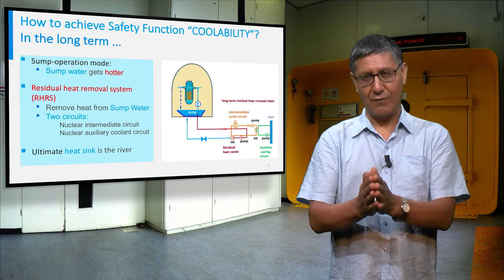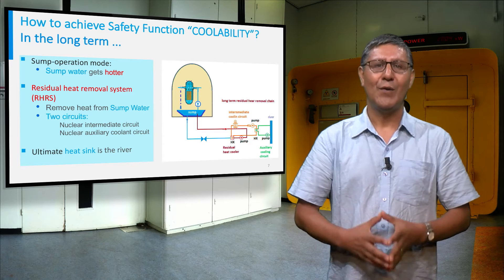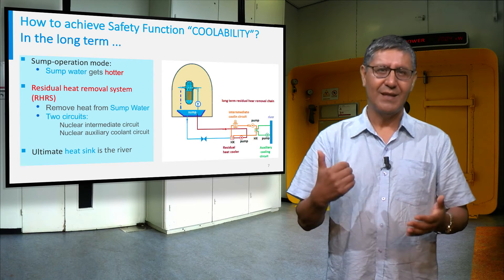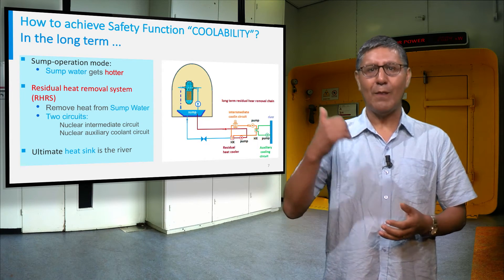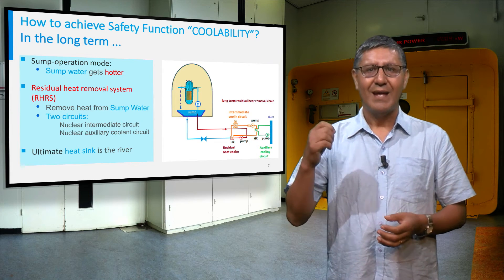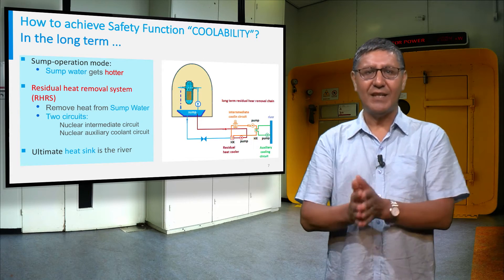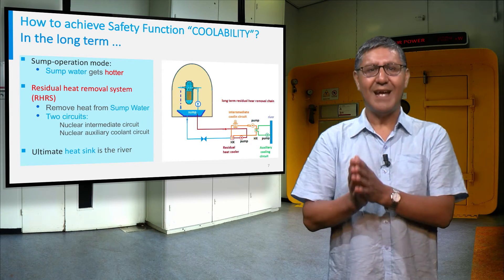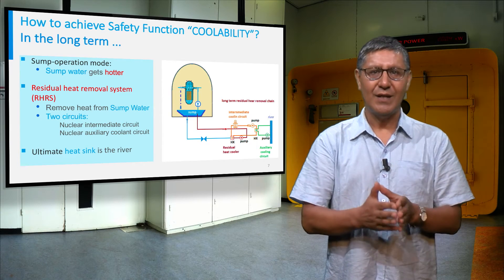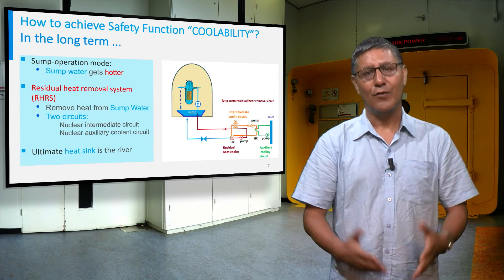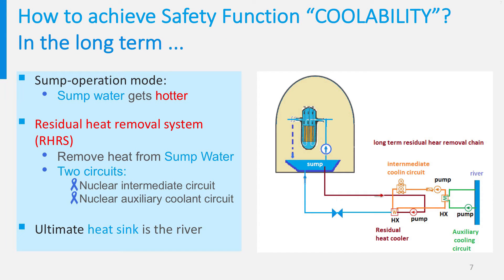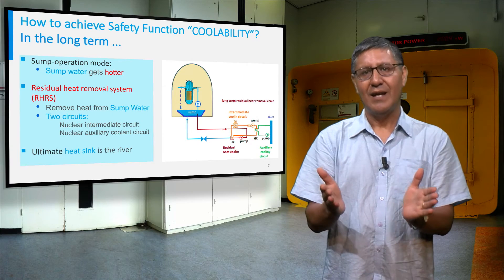The long-term coolability is achieved by the residual heat removal system. Once the flooding tank is empty, the sump operation mode is activated automatically by the reactor control and protection system. Water is injected into the core to remove the heat, and the sump water heats up continuously. The residual heat removal system therefore consists of interconnected circuits with active pumps and heat exchangers to remove heat from the sump water into the final heat sink, which can be a river or an ocean.